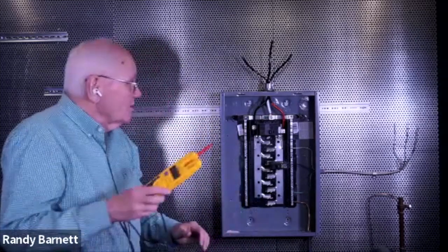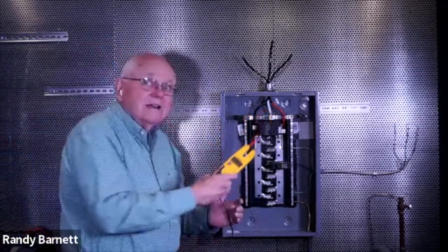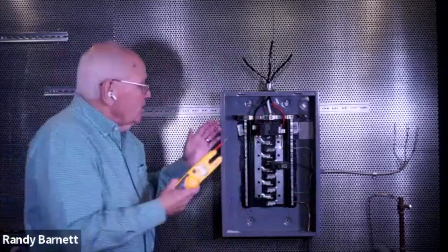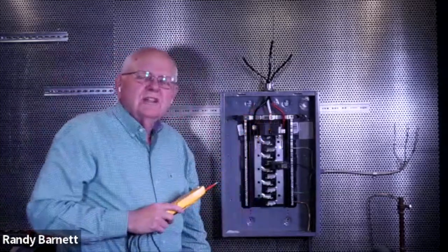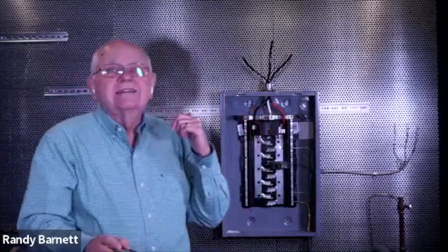I think? Yeah, 200.6(B). It says that for sizes 4 gauge and larger, we can identify them as the grounded conductor at the time of termination by completely encircling that conductor with something white, like white tape, or quite often now you might be using some white heat shrink, something like that. Anyway, so the question is, is that a neutral conductor or not? Well, I don't know. We need to go look at the utility transformer that's supplying us. And yes, certainly in most cases it's going to be.